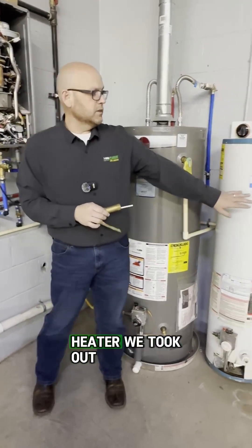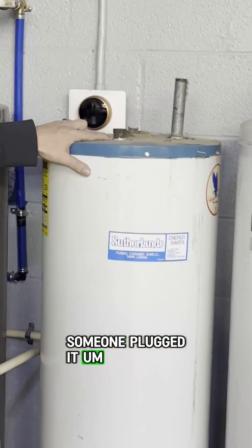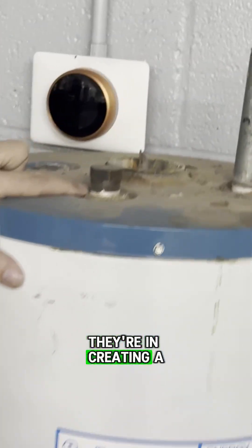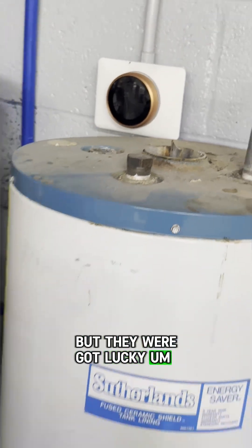This is an old water heater we took out. As you can see, someone plugged the T&P valve — therein creating basically a ticking time bomb. But they got lucky; they never had a problem.